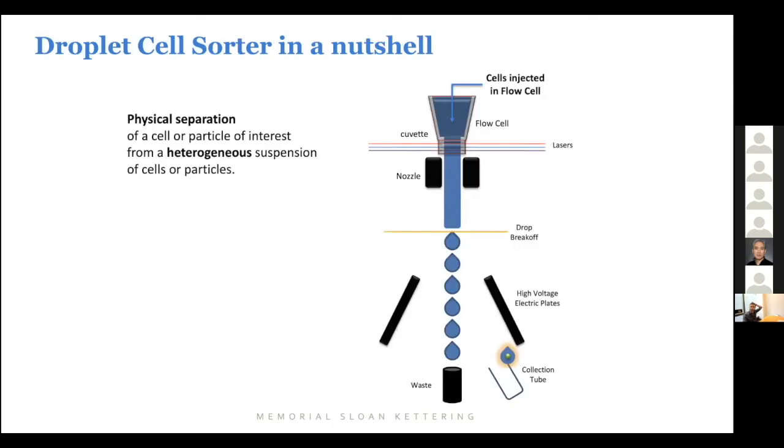How do we know whether we're actually sorting the right population? Or basically the question would be, how do we know that your sorter is charging the right drop at the right time? Now, I can tell you a lot of anecdotal evidence or situations that we've seen. For instance, there was a case many years ago when I was back in Portugal, where we were sorting for one lab, and one of the persons in the lab was sorting B cells from lymph nodes.